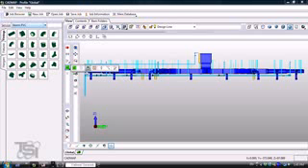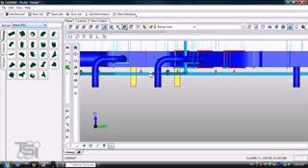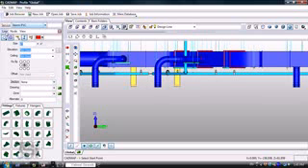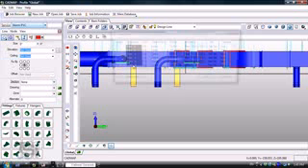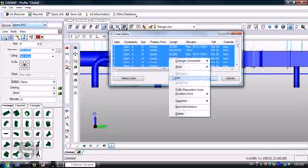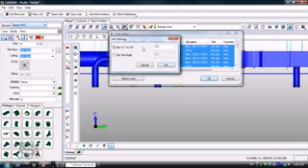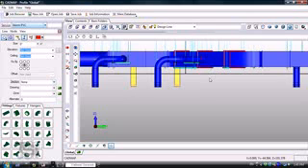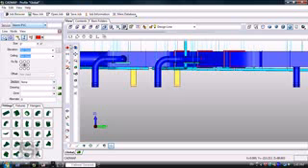So I'll go ahead and modify that system by making this design line active. I'll just take off those piping materials. I'll go to Edit, use a Windows selection set to grab those components. I'm going to right click and go to Fall. I'm going to set that fall here at 1 to 96, and you'll see that line slope out as I autofill that.